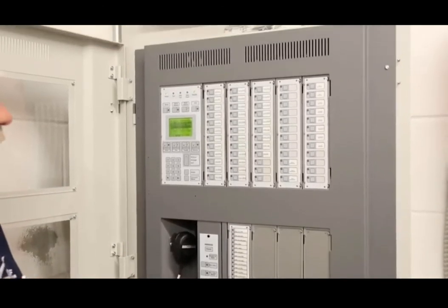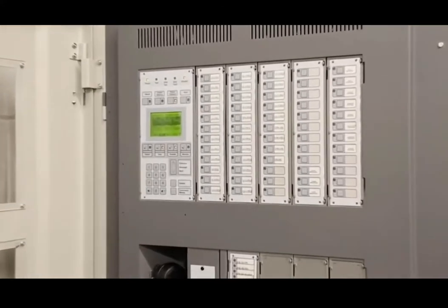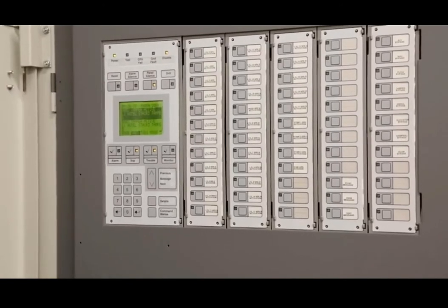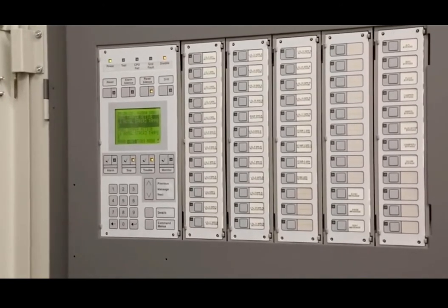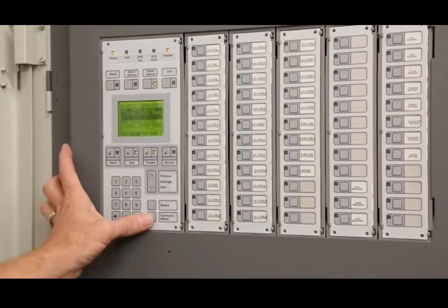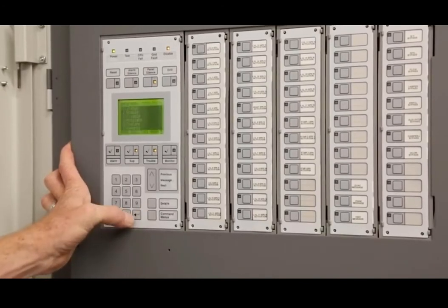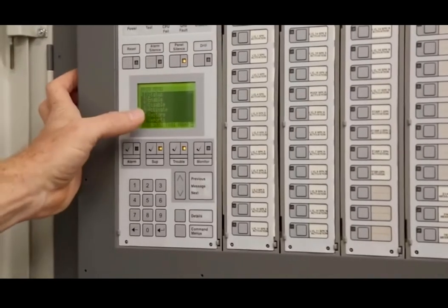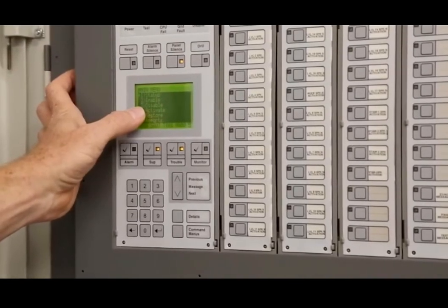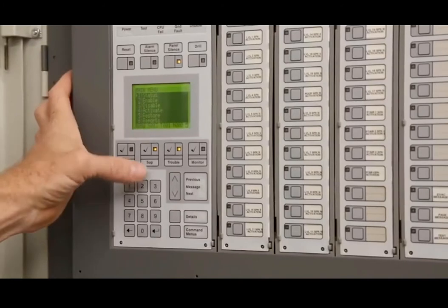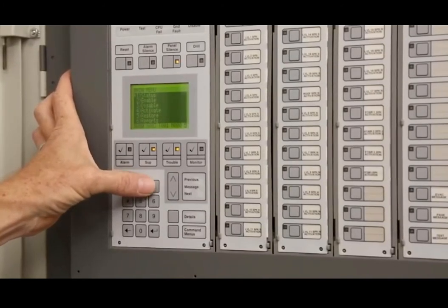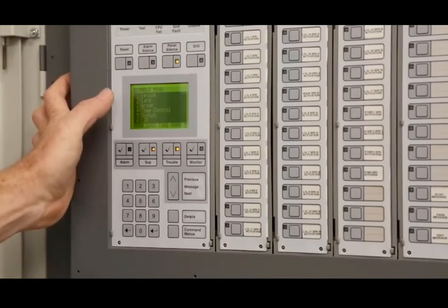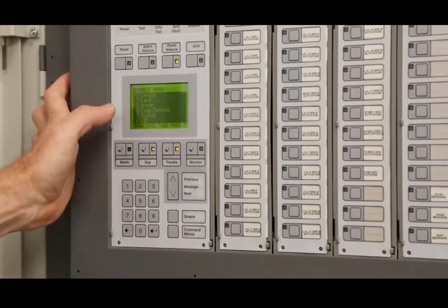If you had a smoke detector that's stuck in alarm, or say a pull station that's sheared off, it's broken, there's addresses on the detectors. So you can go into the keyboard right here. It says menu. It'll say enable, disable. If you want to disable the device, I'm going to just do this one in here. You hit number 3 for disable, and it's going to ask you, do you want to do the device or card? For you all, it's going to be a device.